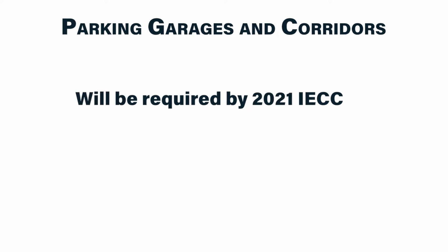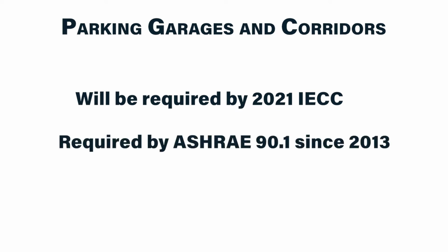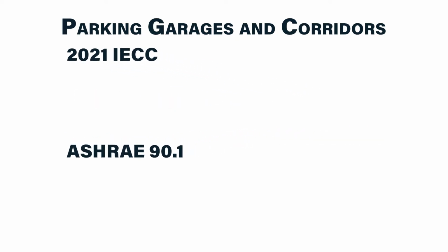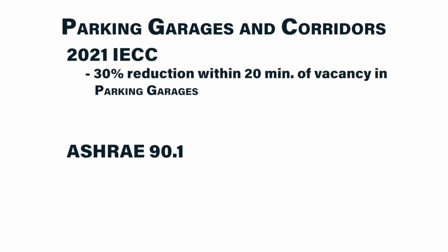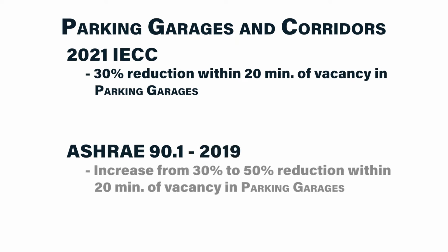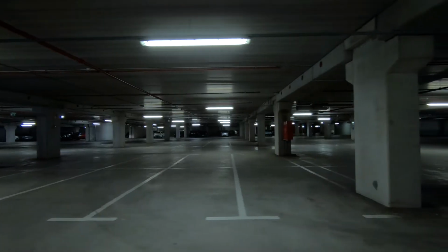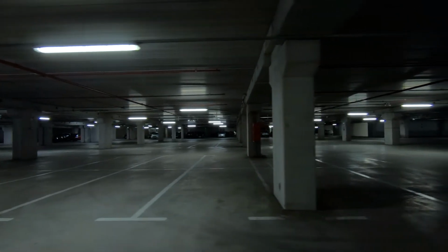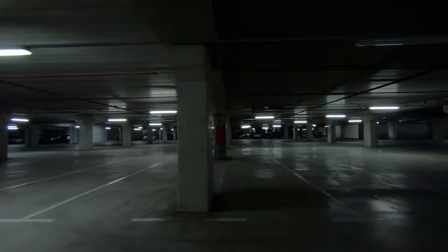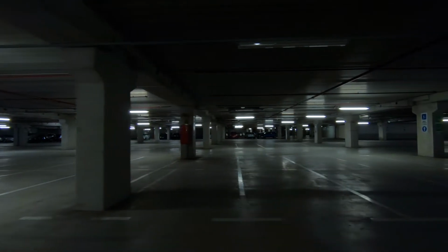but are coming in IECC 2021. And controls in these two space types have been required by ASHRAE 90.1 since 2013. IECC 2021 will be requiring a 30% reduction within 20 minutes of vacancy in parking garages, while ASHRAE 90.1 2019 will increase the current 30% reduction to a 50% reduction.